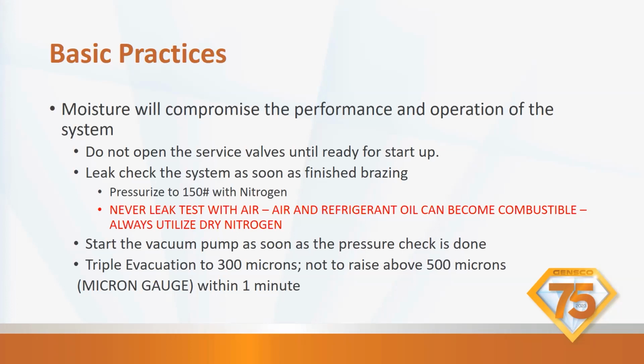Air and refrigerant oil can become combustible. Always use dry nitrogen, and use dry nitrogen every single time you braze, no exceptions. As soon as you're finished with the pressure check, release the pressure, hook up your vacuum pump, do a triple evac down to 300 microns, shut the valve off, go into your unit, shut the gauges off. It should not rise above 500 microns. If it does, you need to turn it back on. If it does it again, you may have a leak or you may have moisture in your system. Okay, those are the two things.